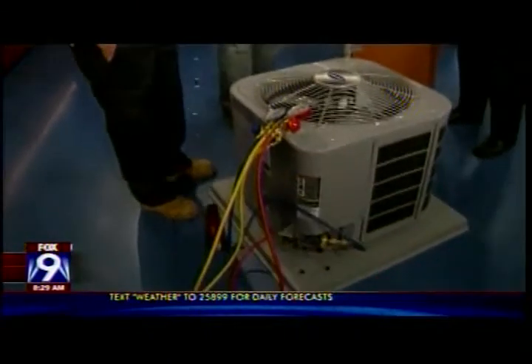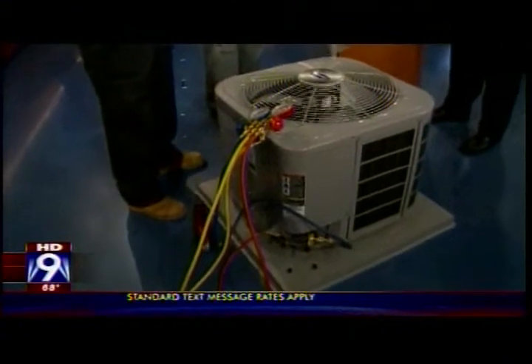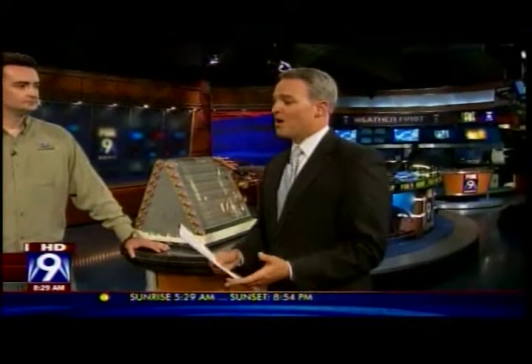Well, for instance, you might find that there's air in the refrigeration line, which would cause excess pressure and eventually burn out your compressor. To replace a compressor, you're looking at about $1,800 — so you'd almost be better off just replacing the whole unit at that point. Yesterday I was on a clean and tune and found air in someone's line and got it out. Talk about efficiency when it comes to our monthly bill — if we get that tune-up for $90, what can that mean for our usage rates?